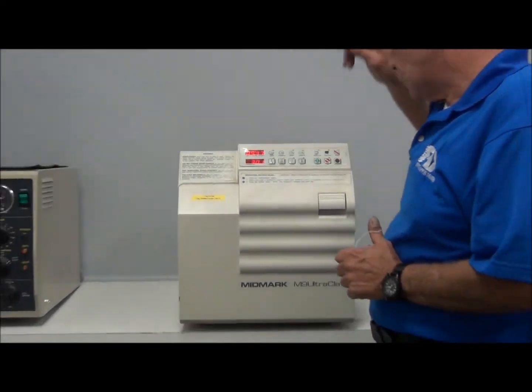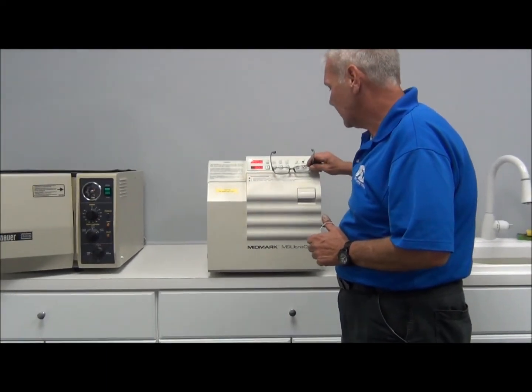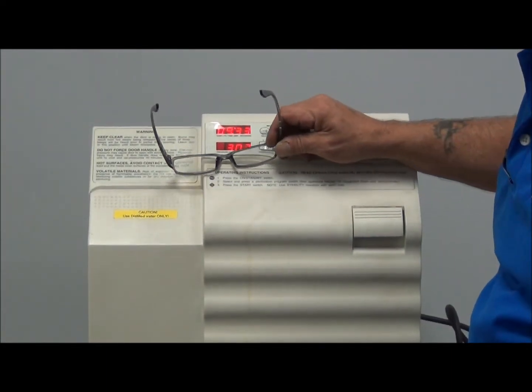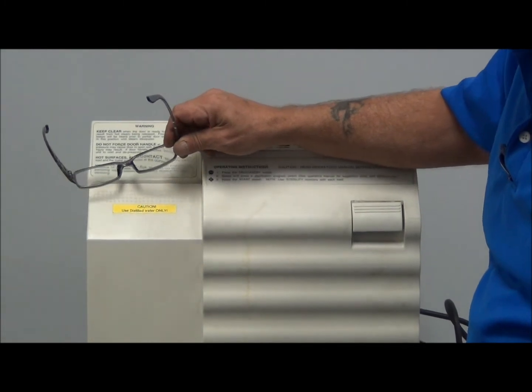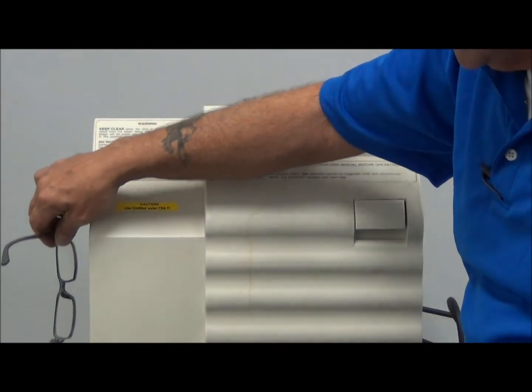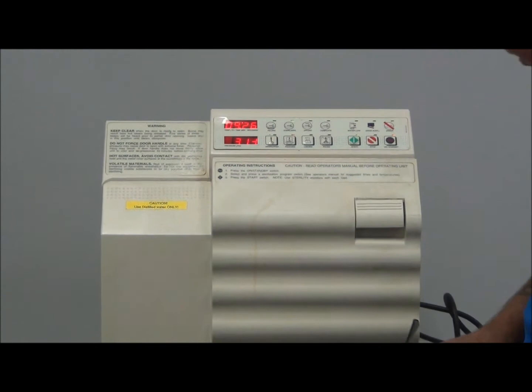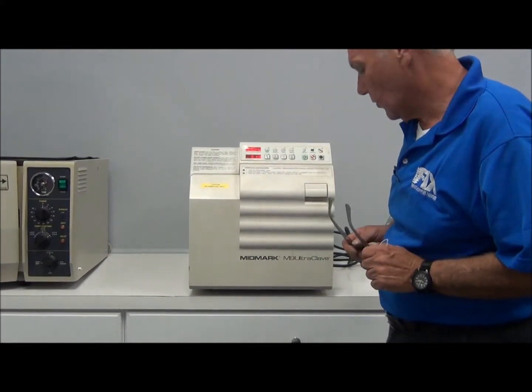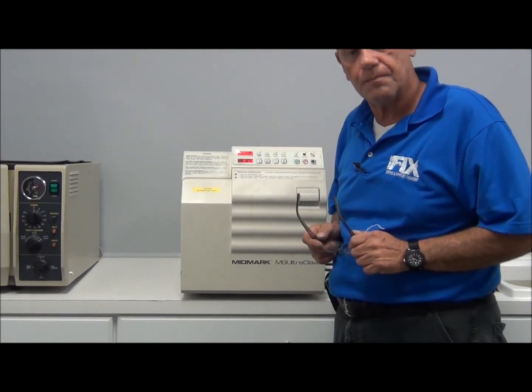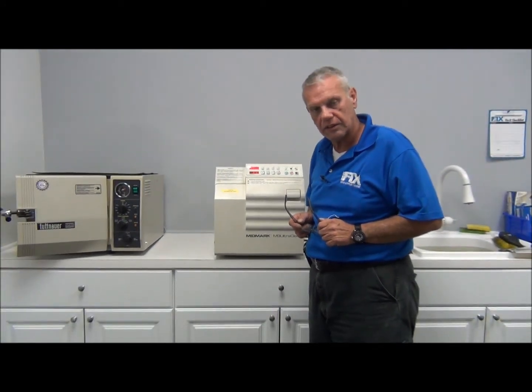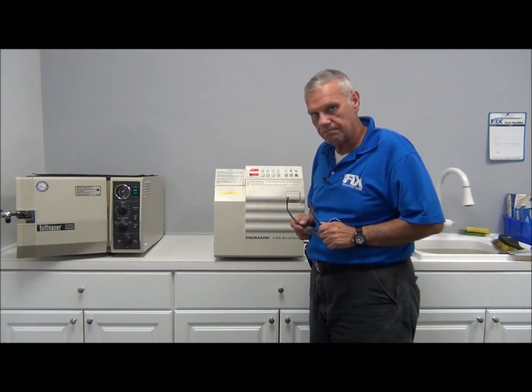Okay, we're going to inspect around the door for leaks. We'll take our glasses or a mirror, go around the door periphery and see if we see any fogging, which we don't. We don't see any water on the counter under the sterilizer. That lets us know the safety valve is held and that the door gasket's good.